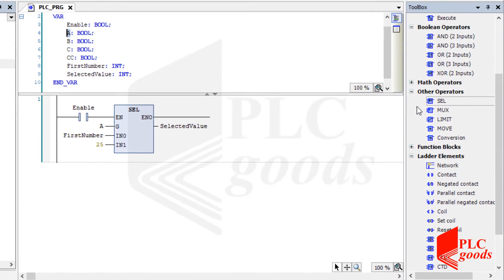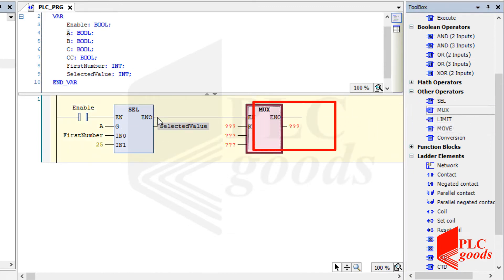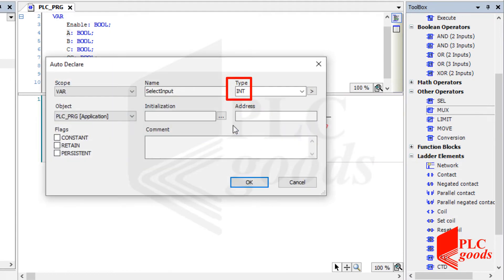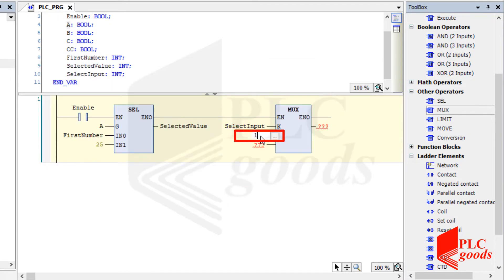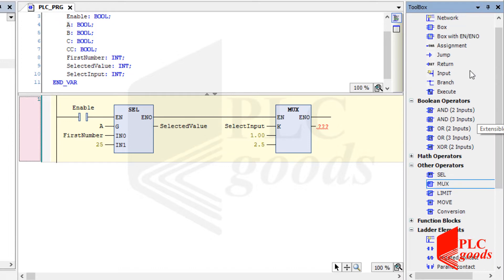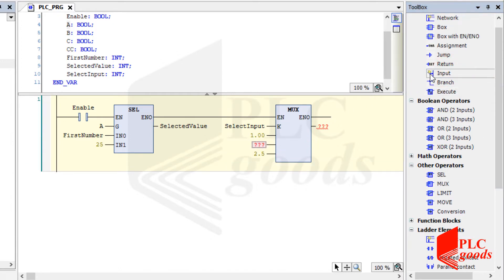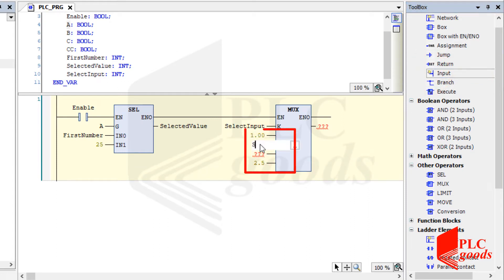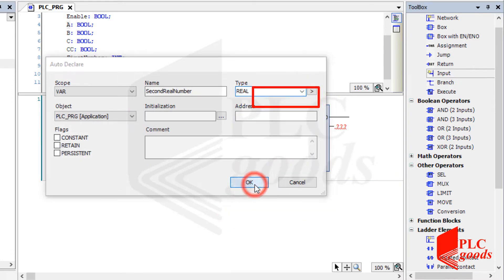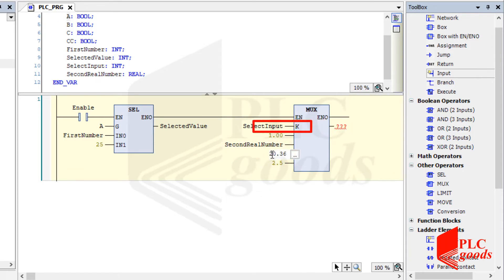The next instruction is called multiplexer. It can be used to select a value or variable. The data type of the second input is integer. If its value is equal to 0, the third input will be selected. If its value is equal to 1, the fourth input will be sent to the other side. The number of inputs can be extended. The data types of the inputs and the output variable must be the same. Let's work with real numbers — Codesys will automatically select the data type for the output variable.